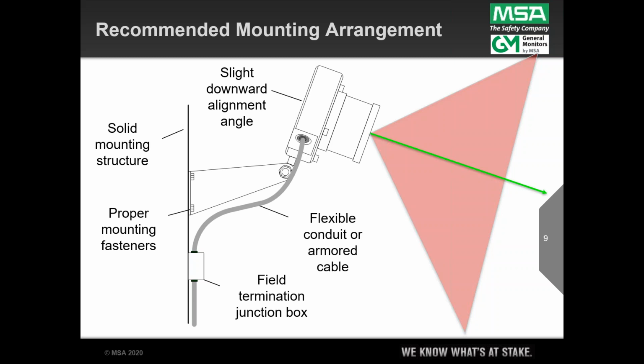If you've got a high level of vibration in your mounting structure, that's not good because it puts modulation into the device right off the bat before it's even seen a fire or seen a hot body. But they actually can withstand a fair amount of vibration, but excessive vibration is a problem. And there's some judgment there, but like I said, all things considered, the more solid you can make that, the better. Also want to see solid mounting fasteners.